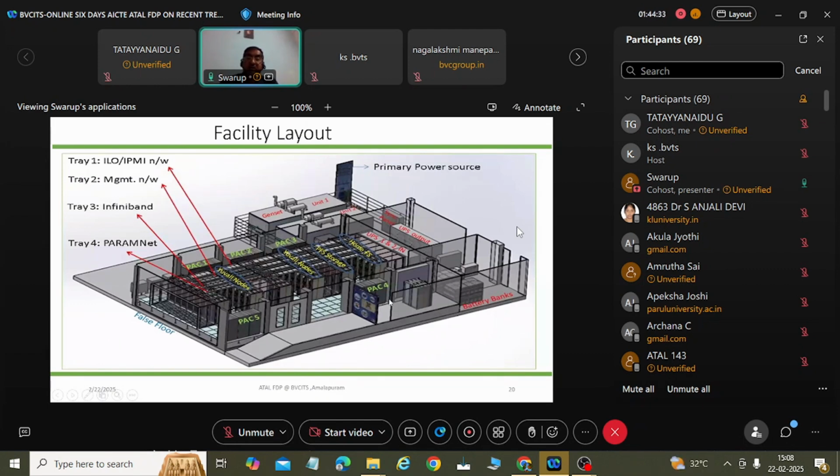I should know the consumption of the storage. I should know the consumption of the nodes. Then I can say what is the overall power consumed for the entire data center divided by only the IT load. That gives me the PUE.